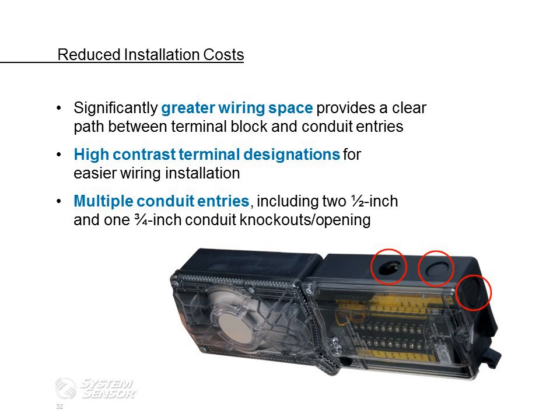This product also has greater wiring space. There's more space on the power board side, so it's much easier to wire. We have a high contrast terminal designation. It's a bright neon yellow with black lettering, so it's a little easier to see and read. And we have multiple conduit entries that include two half-inch and one three-quarter-inch conduit knockout.